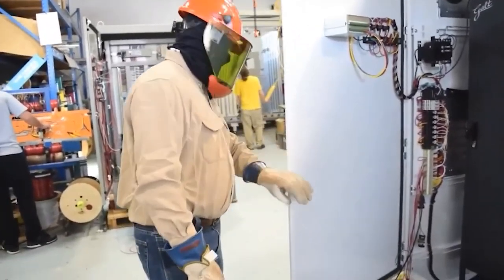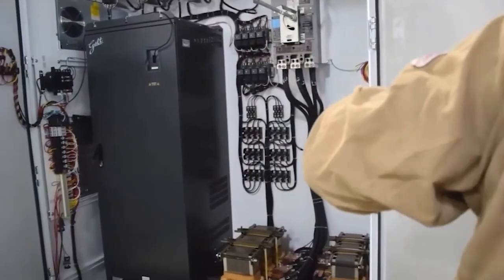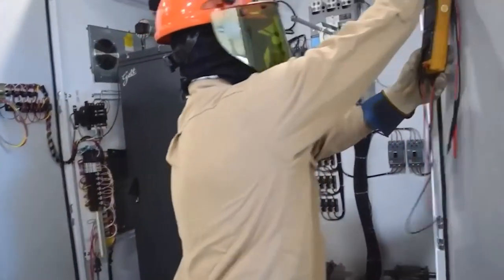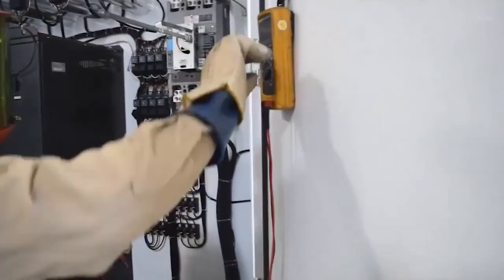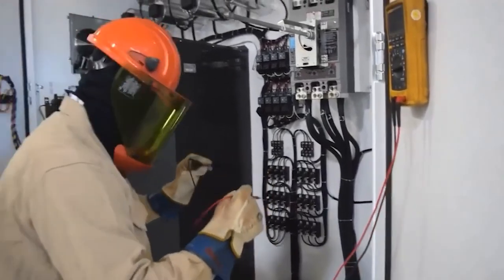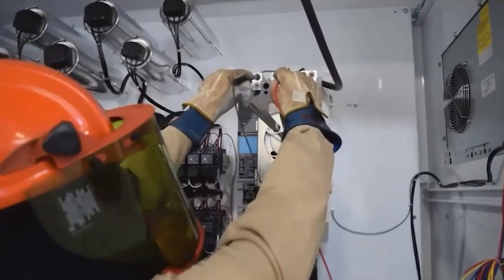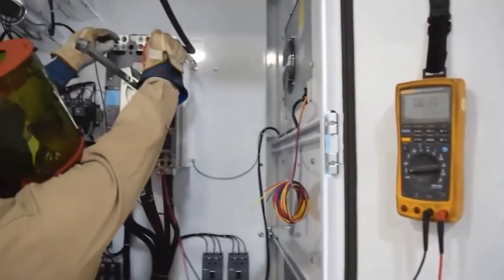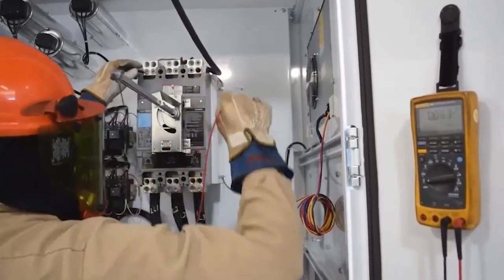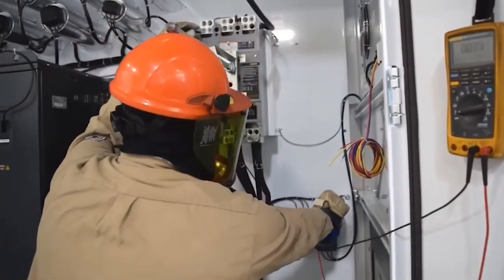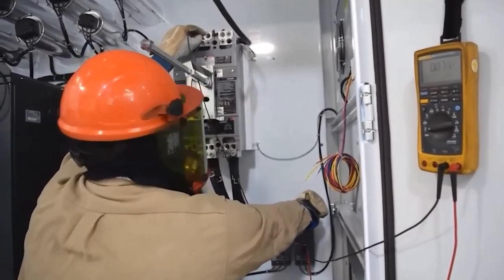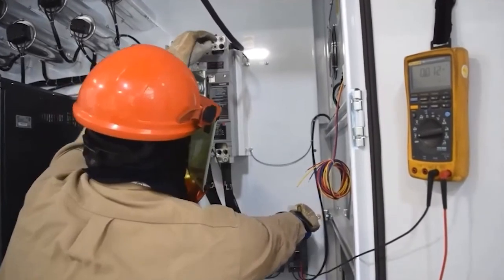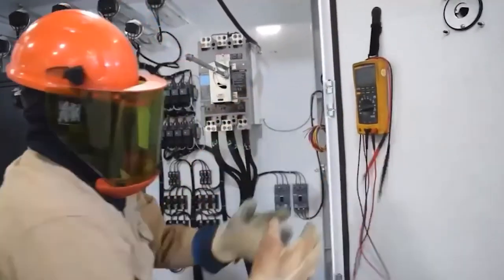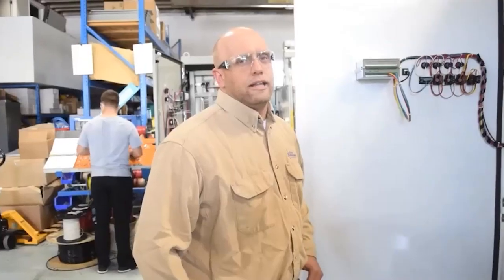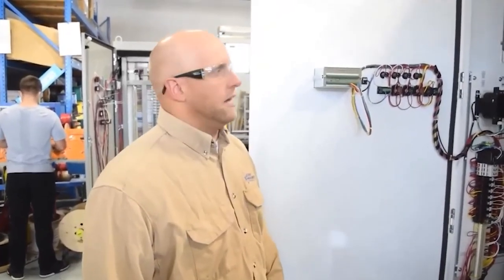All right, so the first thing we want to do is make sure when we get inside of one of these cabinets that we get the power turned off and that we verified it properly. To verify that you have all your power turned off, you need to put your proper PPE on. You need to go find your meter, which I left on the side of the door, so I had to go pick it up. And then we're going to measure our incoming voltage, and we're going to measure from A to B, B to C, C to A. Make sure that we've got 0 volts. And then also, we're going to measure from A to ground, B to ground, C to ground, and also make sure that we have a 0 volt reading. So once we've measured all that, then you can go ahead and remove your PPE now that you have everything off. And then we can go ahead and get inside the cabinet.